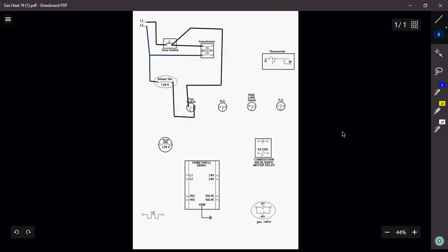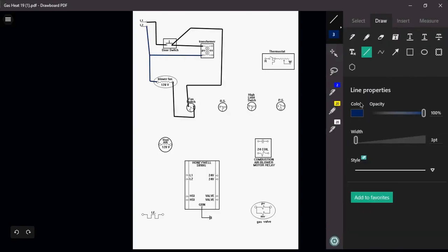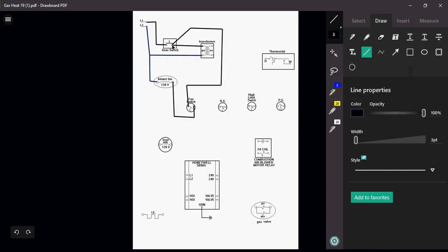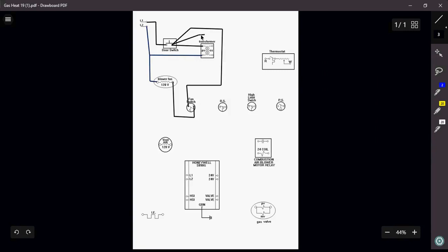So where else do I need to go? Well, I still have to take care of this guy, my vent motor, also known as my inducer motor. So I need to be able to have my combustion air blower motor relay control this guy. So in order to do that, I need to again bring my power from my door switch. And again, we're just going to go like this.